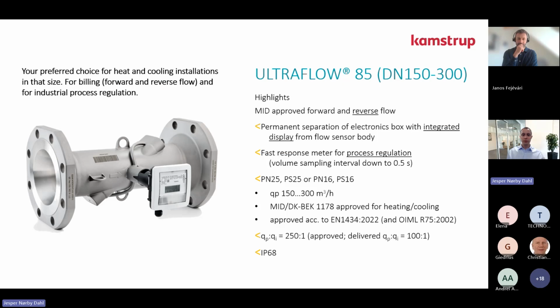ULTRAFLOW 85, so that's DN150 to 300. Some of the highlights: it's MID approved, both in forward direction and in reverse direction. We have now added this permanent separation from the electronics casing here. So this is standard. It's a fast response, so it measures down to 0.5 seconds now. We have PN25 or PN16 connections. It has MID approval and also the Danish cooling approval.